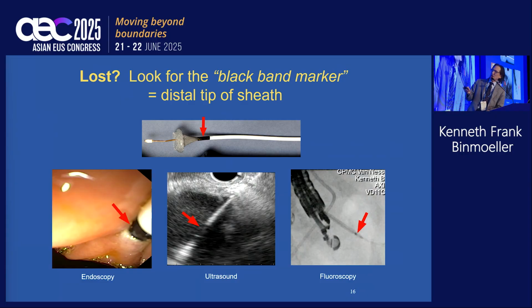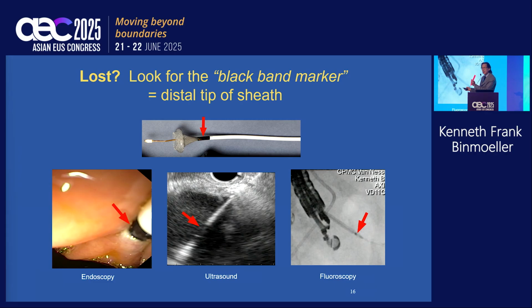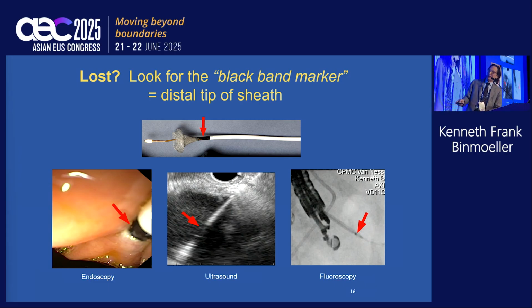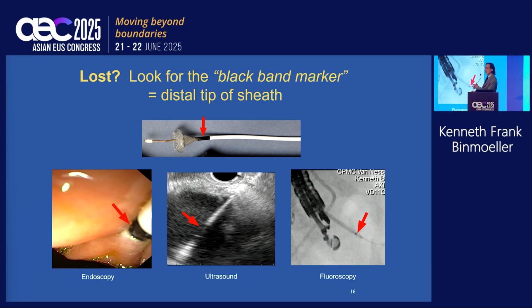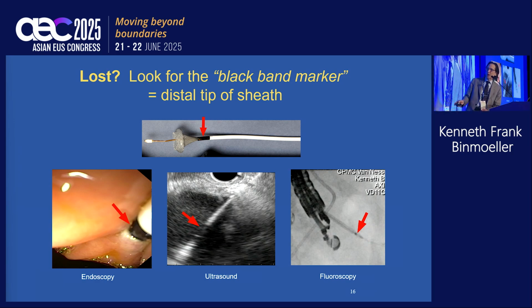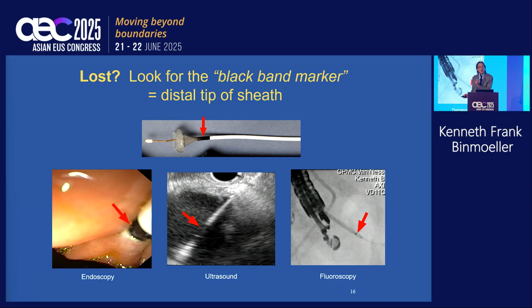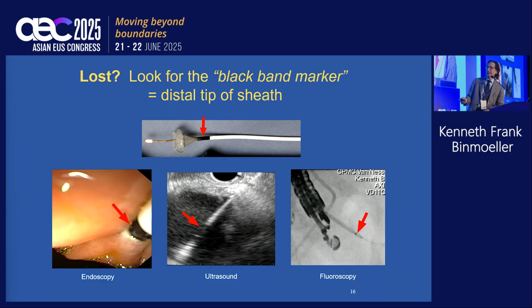If you ever get lost, look for the black band marker. That indicates the distal tip of the sheath. You need to know where the distal tip of your sheath is at all times. And you can see it endoscopically here. Here's that black mark. That's where the sheath ends. You can see it on ultrasound. We made it so that it's visible as an echo-free region. This is where the distal tip of the sheath is. So if you look for it, you will see it. And on fluoroscopy, because it's radiodense, you will see that black mark. So you will always know where the distal end of that sheath is located.